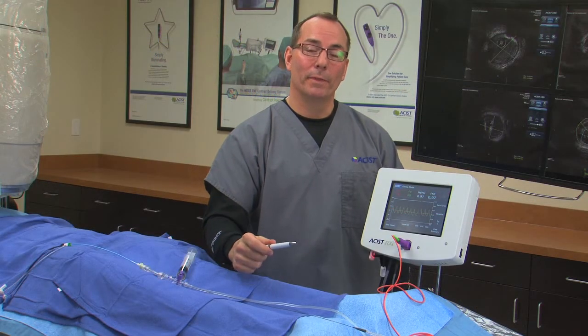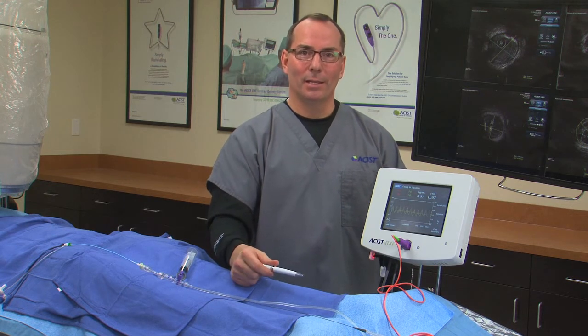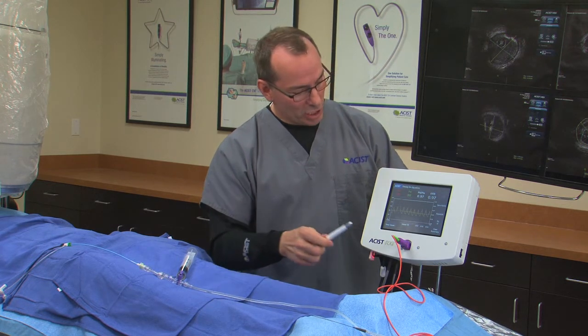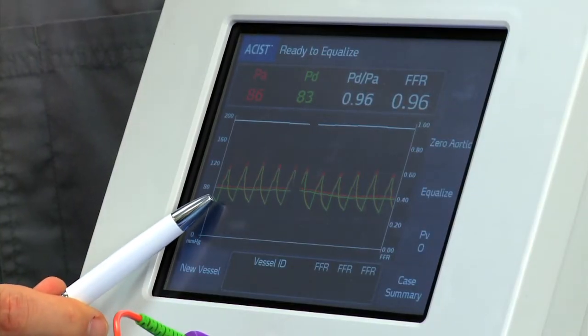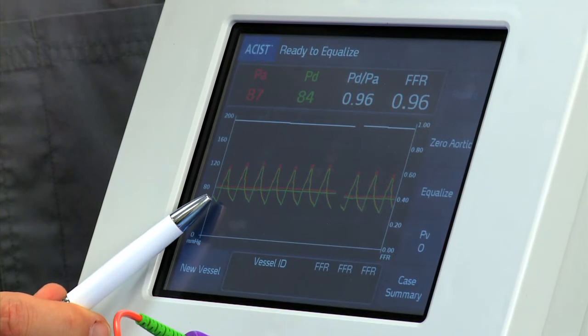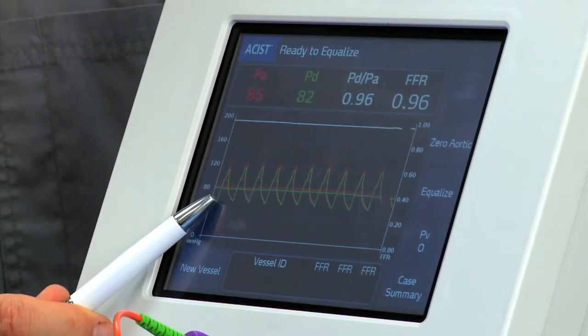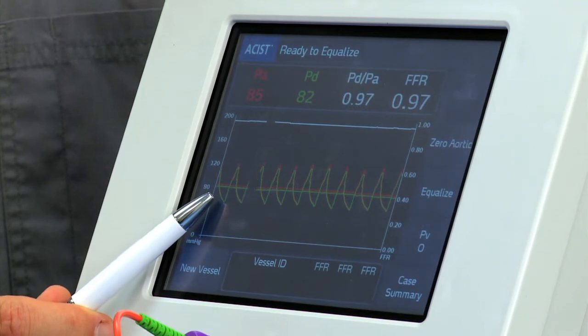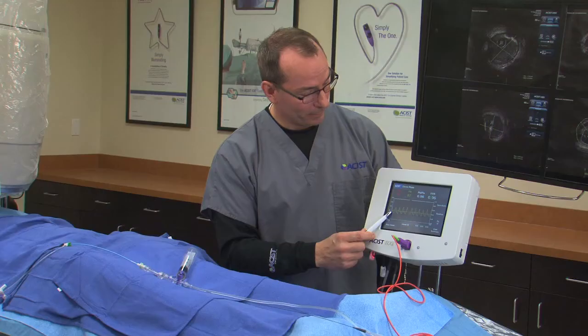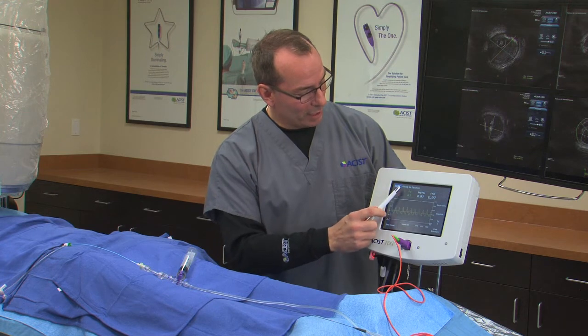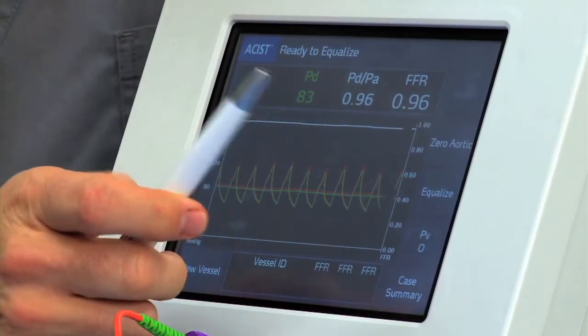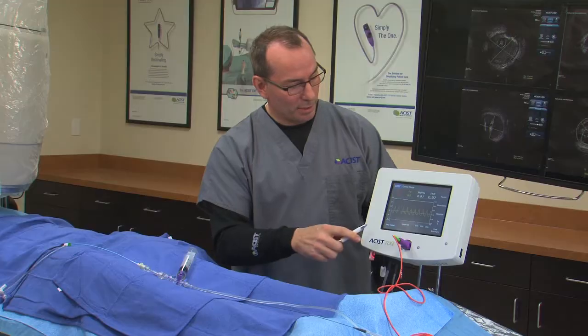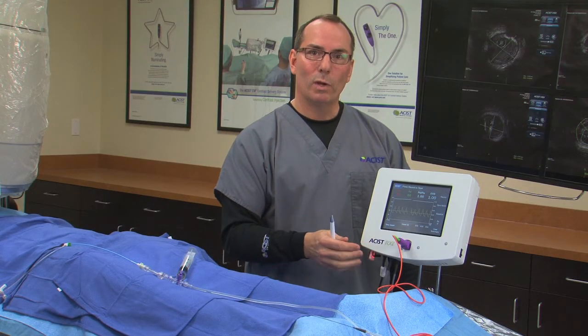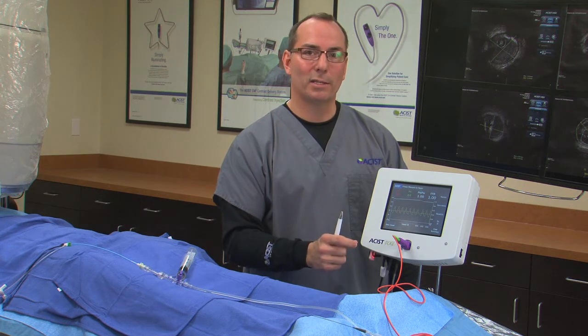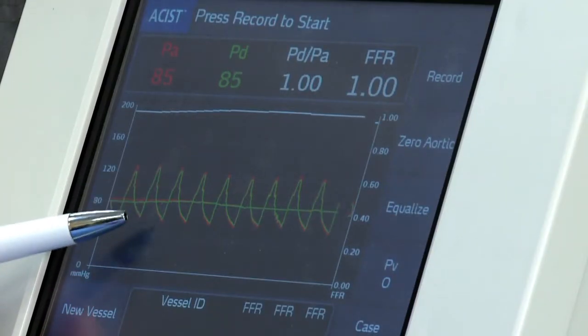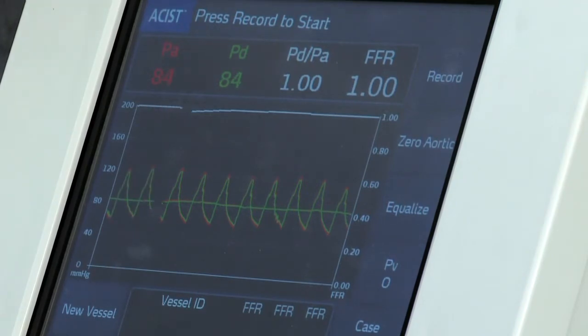Now we have the Navvus catheter sensor in the body positioned at the guide catheter tip. And you can see both pressure waveforms are displayed on the screen. The red is the patient's aortic pressure. The green is the Navvus catheter pressure as measured by the fiber optic transducer. You notice at the top of the screen it says ready to equalize. By pressing equalize, we're telling the system whatever that aortic pressure is, we want the Navvus catheter pressure to be exactly the same. And that will superimpose those two pressures on the screen.